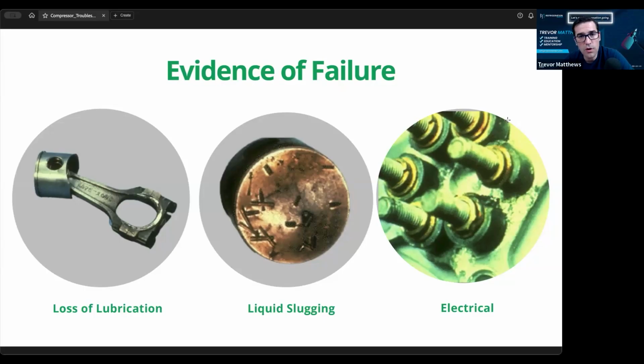But the more you work on the compressors, the more you get to see and the more you listen to them. I know technicians that can walk right into a rack room where a normal person walks in and says, oh my God, this is loud. They walk in and say, compressor 3 is knocking, there's something wrong with compressor 3 or compressor 4. And most people are like, I don't know, I don't hear anything, it just sounds like a loud motor. So you'll get that over time as you work more on these systems.